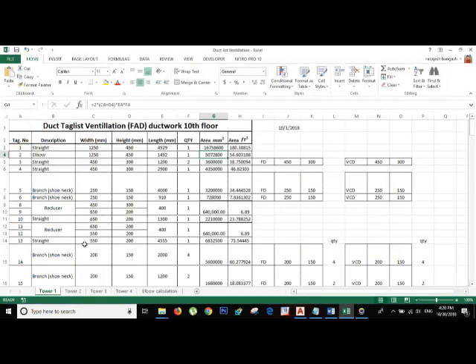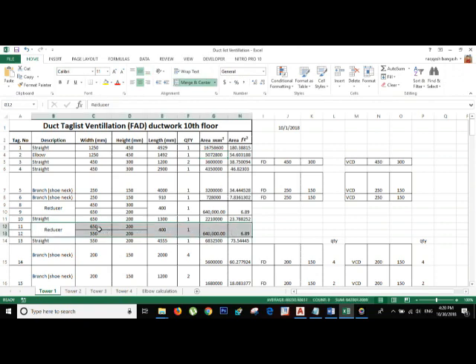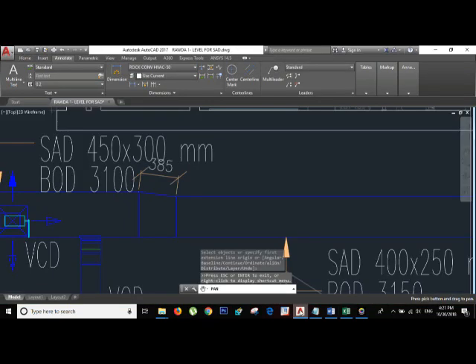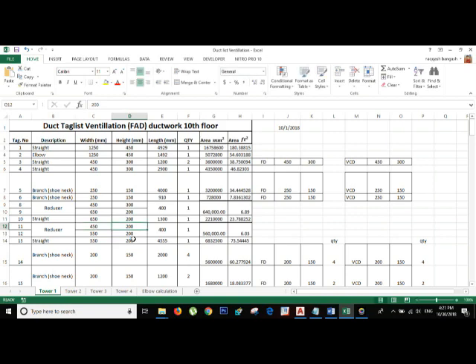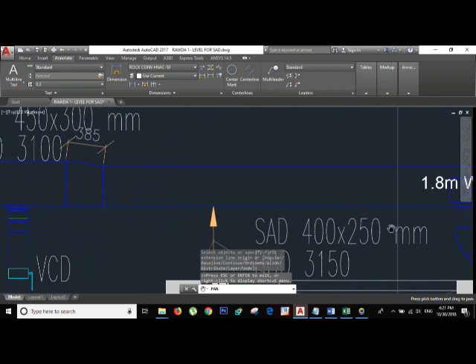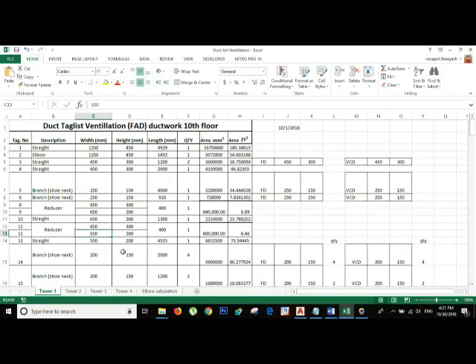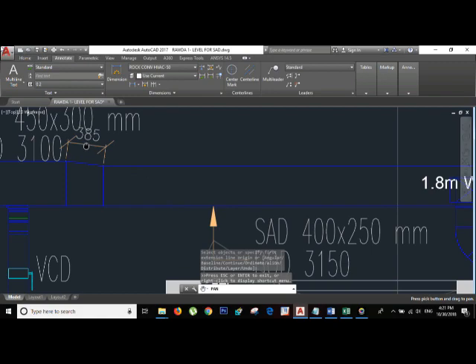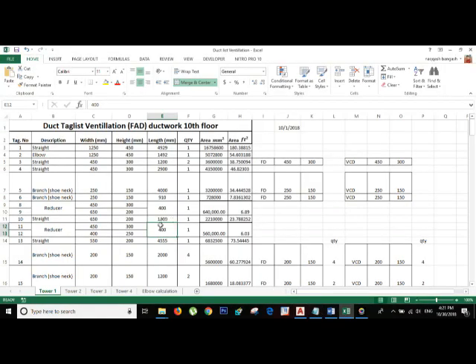Let's look at the formula in the Excel sheet. For the reducer, first we put one side: 450 by 300, where 450 is Width 1 and 300 is Height 1. Then Width 2 is 400 and Height 2 is 250. So the reducer goes from 450×300 on one side down to 400×250 on the reduced side, and its length is 385.